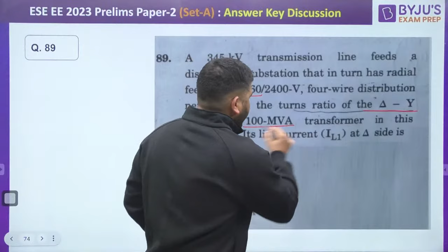Now we need to calculate the line current on the delta side. We know 100 MVA, where MVA means 10 to the power 6, has to be equal to root 3 times VL times IL. So from here we can calculate IL if we know VL. But VL is not known to us directly. If we take this given value as VL, it's problematic, because I'm not sure whether it's actually the transformer rating. It's possible that this radial feed rating isn't for the transformer at all, so we need to consider that possibility first.